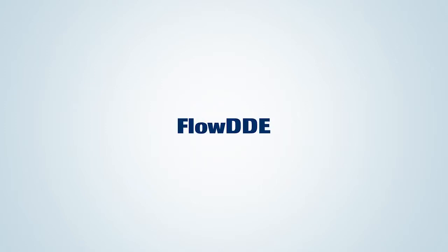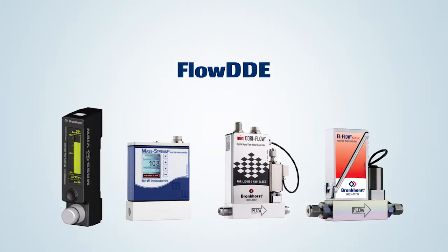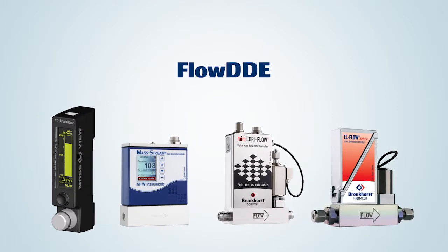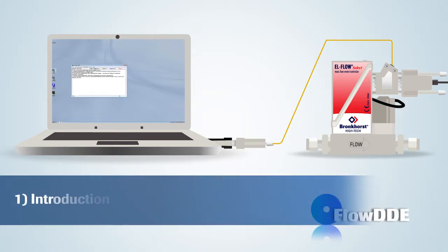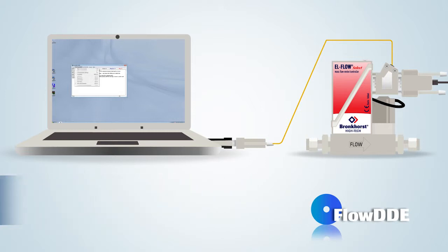FlowDDE is a dynamic data exchange server, an easy connection between Windows applications and Bronkhorst digital instruments. DDE provides a basic level of inter-process communication between Windows applications. By using DDE commands sent by software to FlowDDE, data can be sent to or requested from digital instruments. FlowDDE handles all communication to the instrument and provides the data to applications.